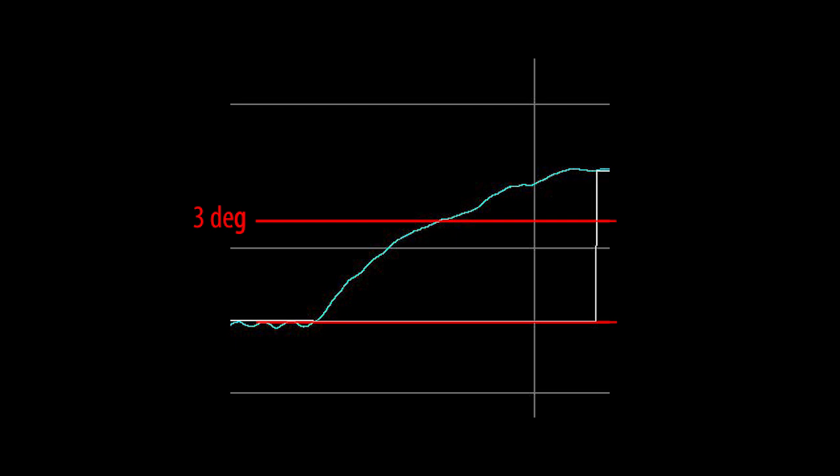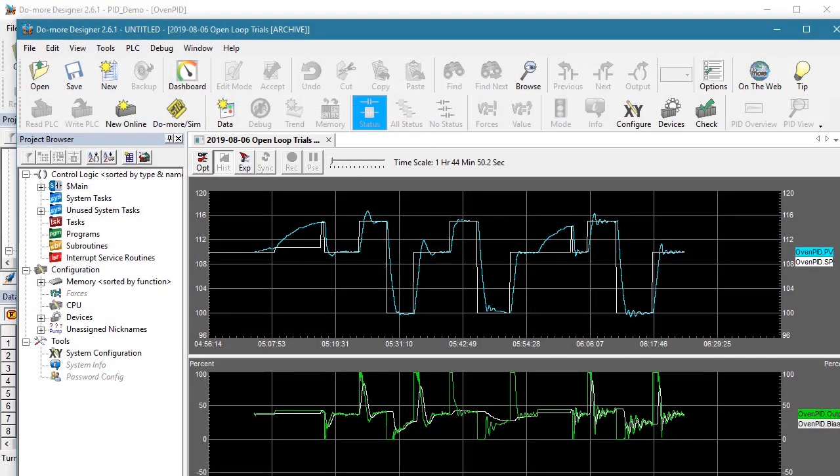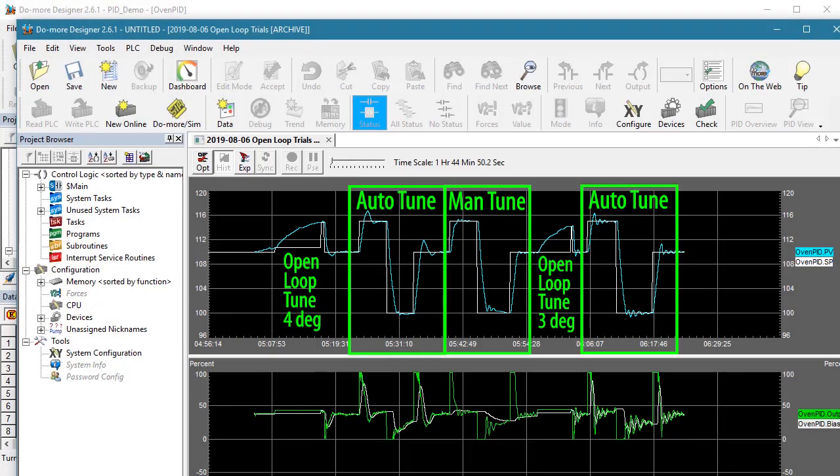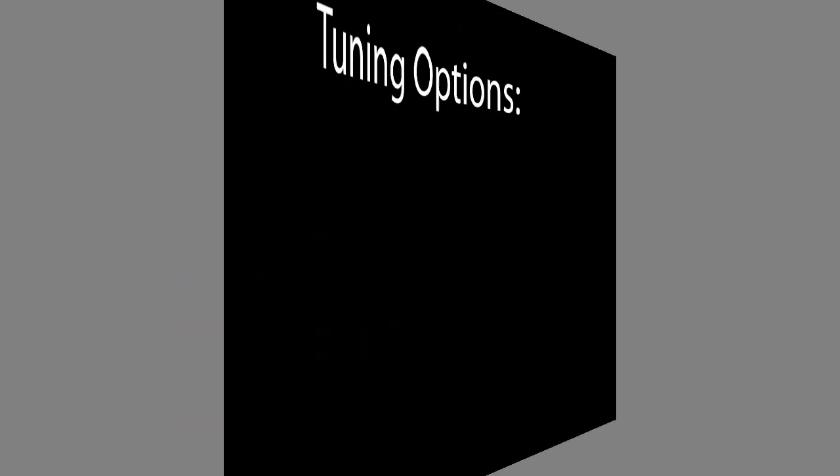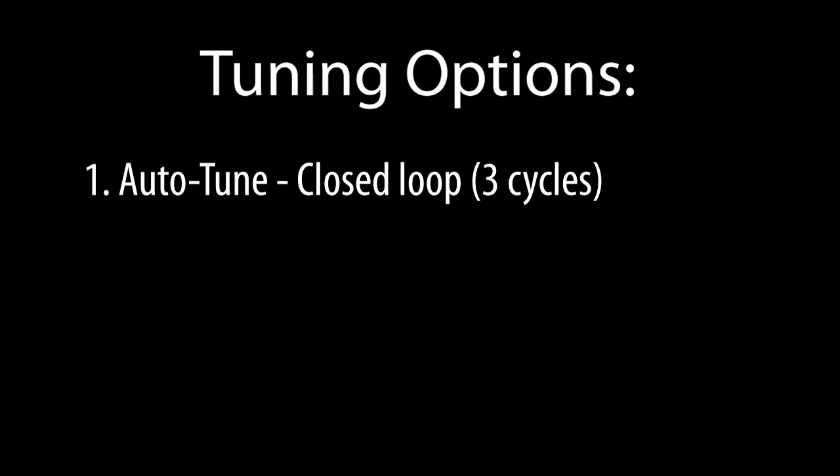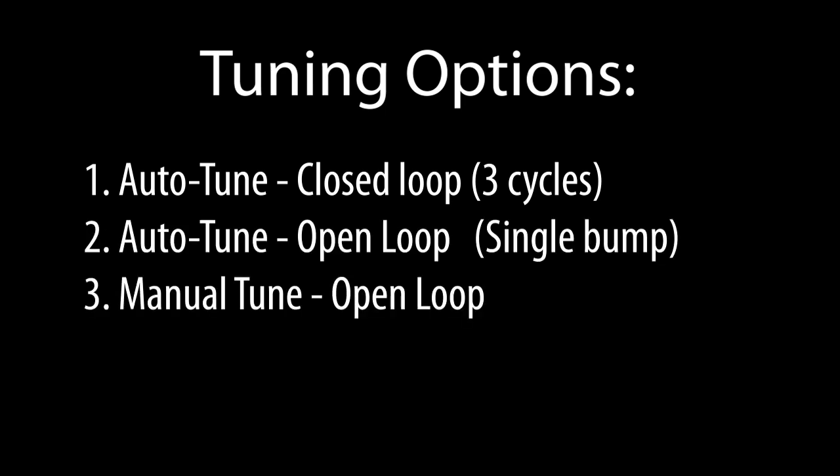And it's exactly this kind of anomaly that drives Auto-Tune nuts because it only has this limited data to work with. When we manually tune, we can see the bigger picture and we are in a better position to make judgements on what's going on. Even so, Do-More Designer does an amazing job – remember this overshoots only a degree or two. I'll take that any day of the week. So now you have several ways you can tune a PID Loop. Closed Loop Auto-Tune, Open Loop Auto-Tune or manually using the open loop method we use in this video.